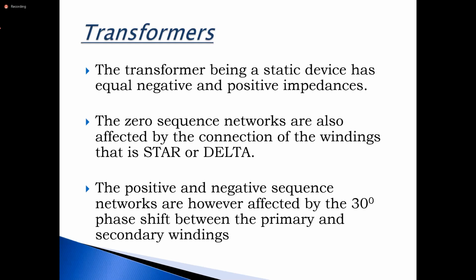The challenge, as I mentioned briefly just now, is in determining your zero sequence network, because the zero sequence is going to be impacted by whether you're dealing with a star winding or a delta winding. All right?